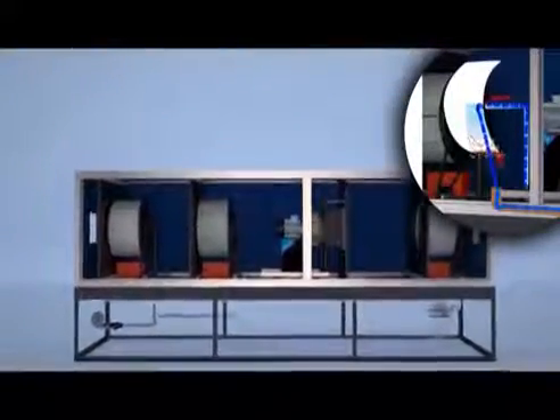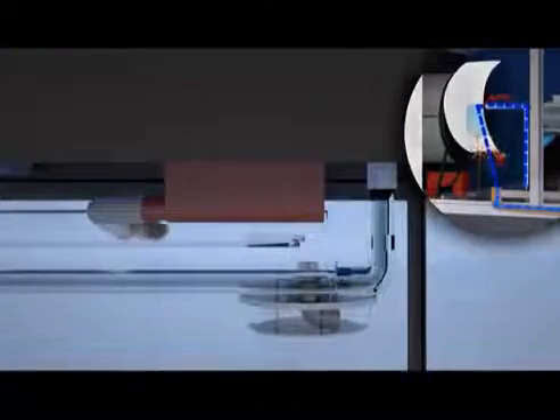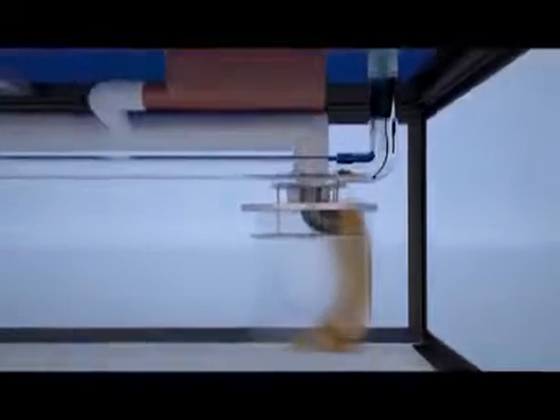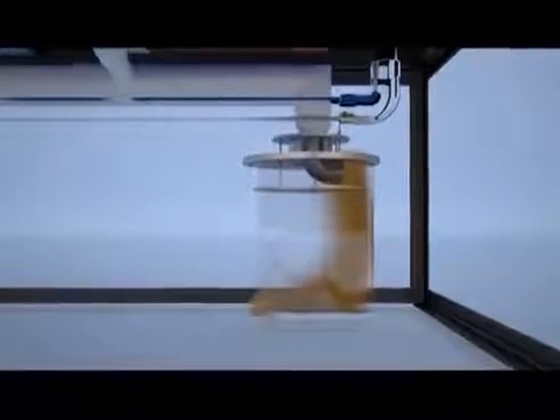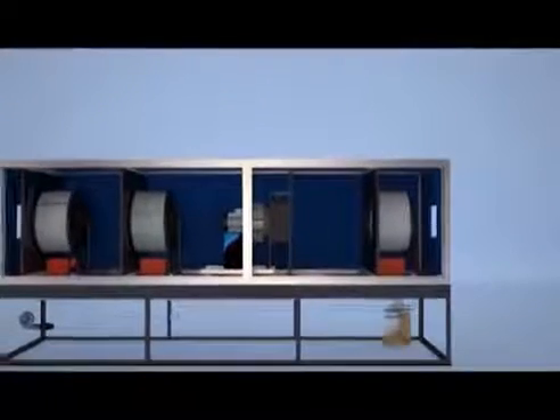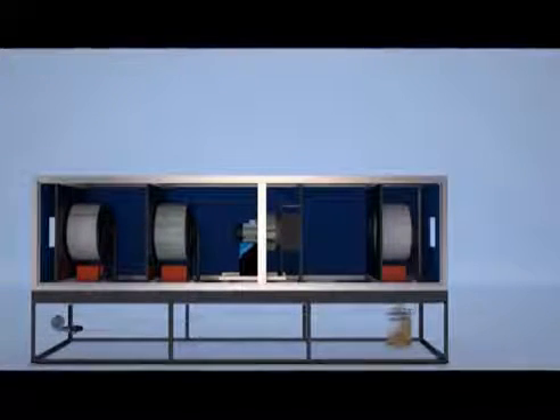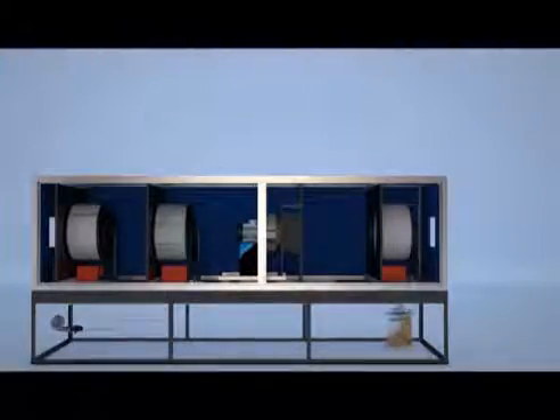At the bottom of the AHU, we provide a suction point, which is connected to the pulse jet dust collector. The dust collector sucks the dust from the air that parted from the filter. No dust particles remain in the AHU, and the filter is continuously free from any dust particles. Thus the system remains clean and the AHU remains totally clean.